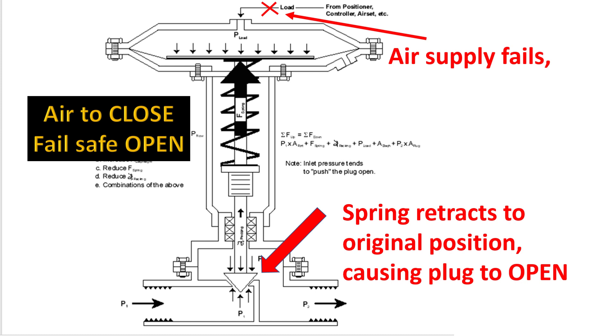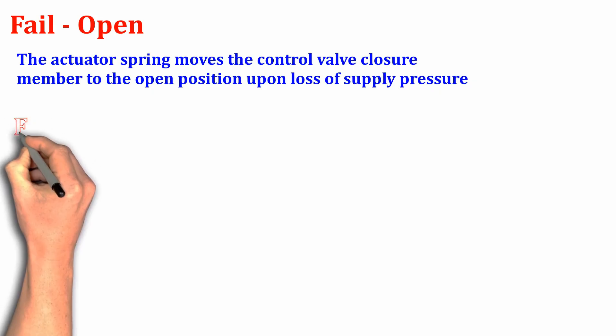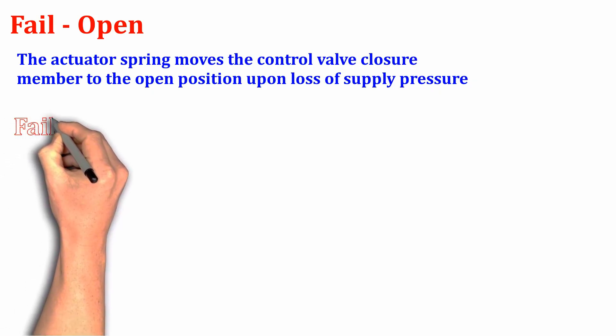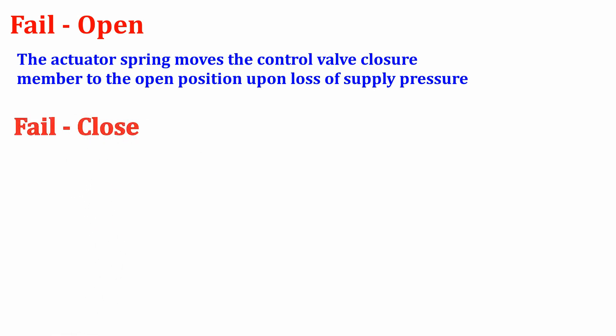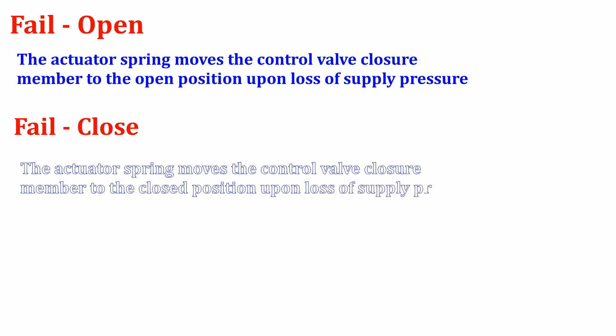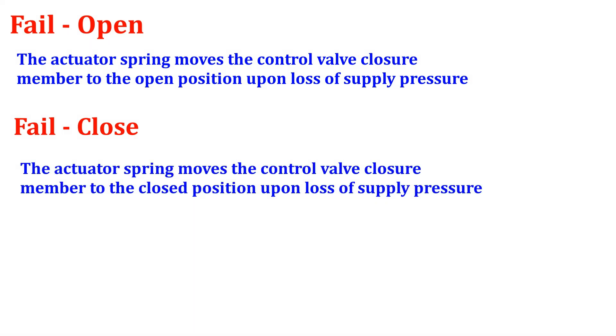When air fails, the spring automatically retracts to its original position, causing the plug to open. This is how your failsafe open actuator works. Next is the failsafe close condition — in this mode, the actuator spring moves the valve closure member to the closed position upon loss of supply air, which is basically the vice versa of failsafe open mode.